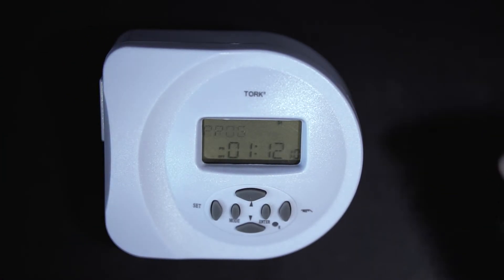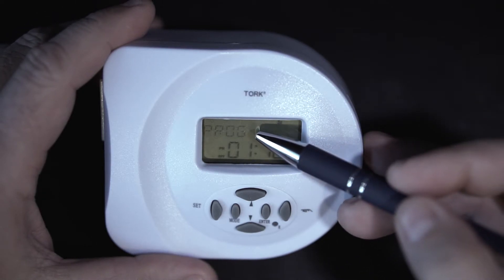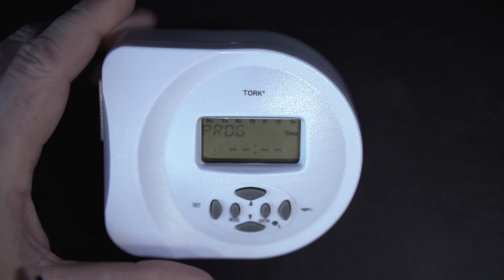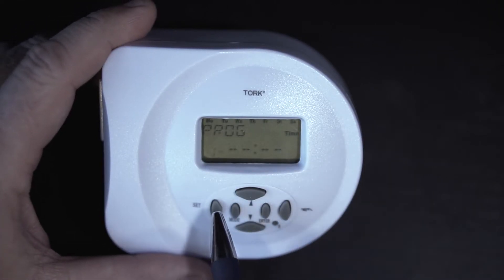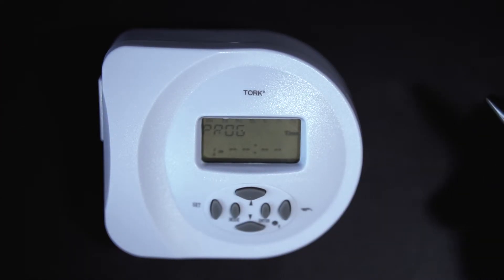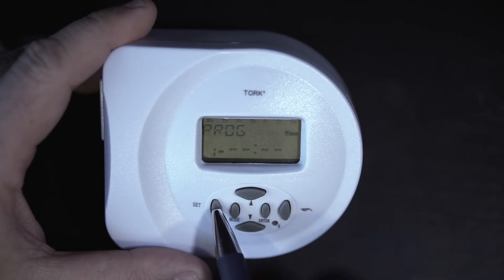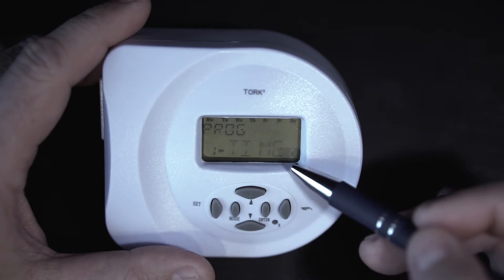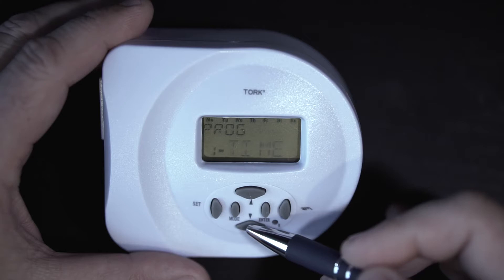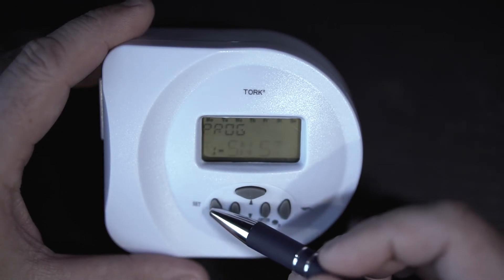What's great about this TORK timer is it automatically has sunrise and sunset set up as the first options, making it very easy to cycle through. With Program flashing, hit Enter to go into that mode and you'll see Program 1 On. Hit Yes to accept that as the first setting and you'll notice all seven days flash at the top of the screen. For our lighting purposes we want it on all seven days, so hit Set to accept. Then use the up and down arrows until you see Sunset — SNST is our sunset start time — and hit Set.